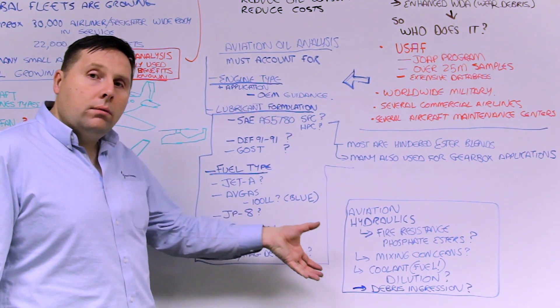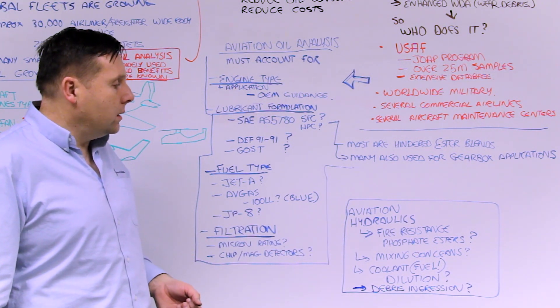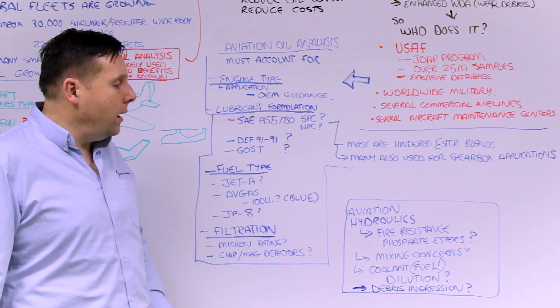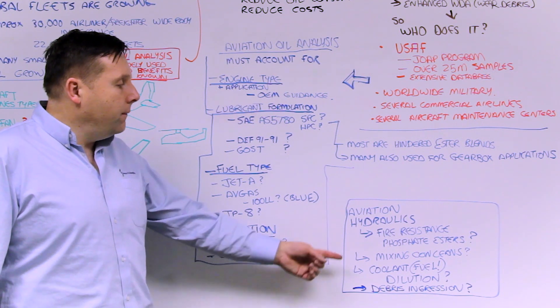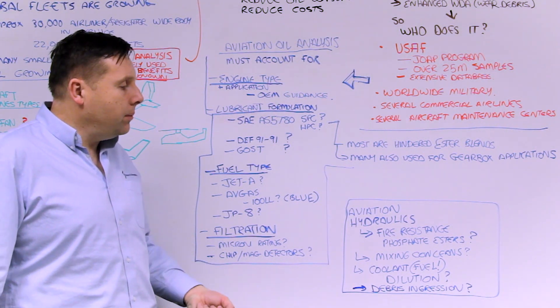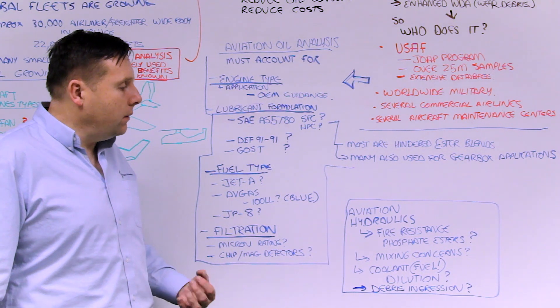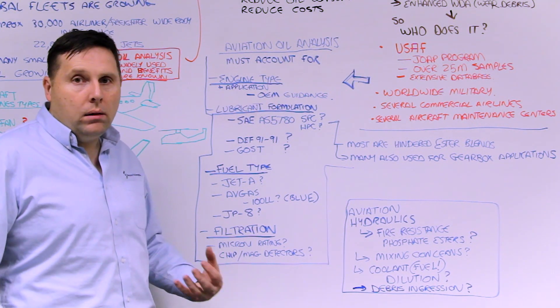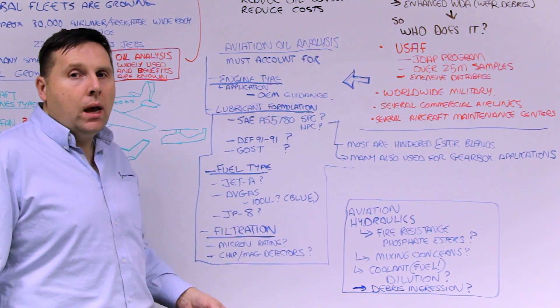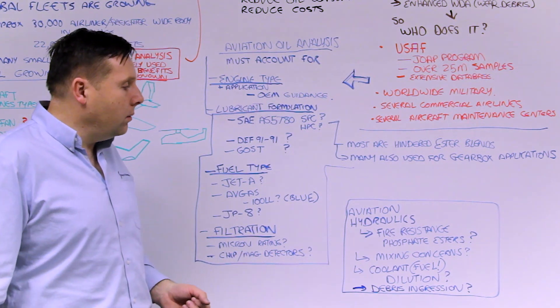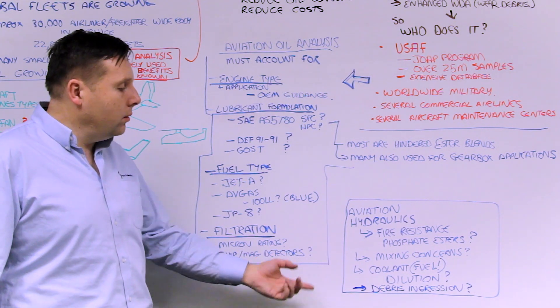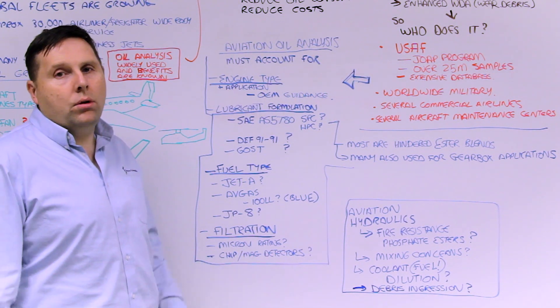Aviation hydraulics are another area of concern for oil analysis. The hydraulics must have fire resistance for prevention of fires in the event of accidents. Phosphate esters are widely used in those situations, designed for a specific application. You do not want mixing of hydraulic fluids — a mineral-base with a phosphate ester. You also need to be concerned about coolant and dilution getting in, or debris ingression.